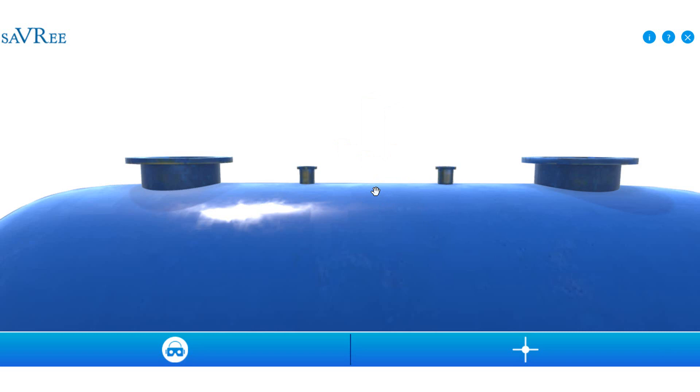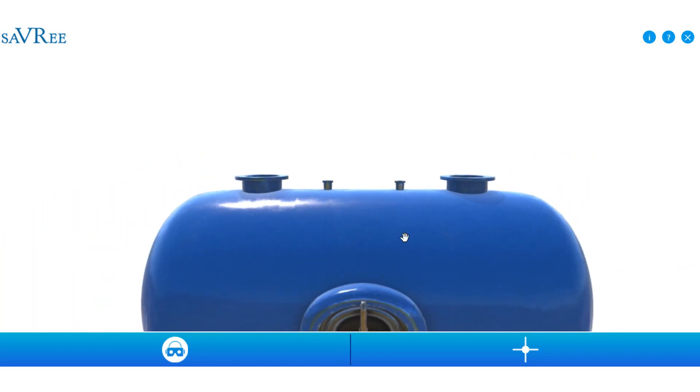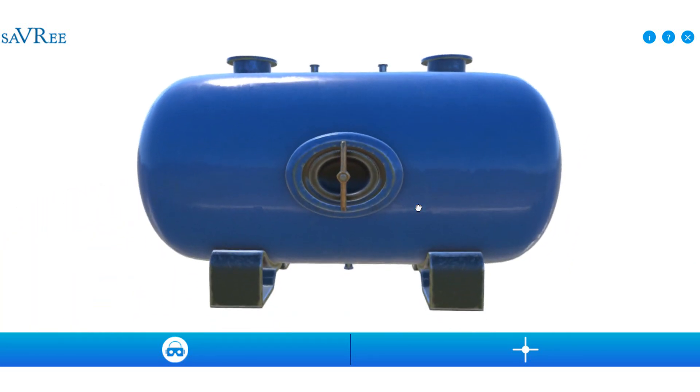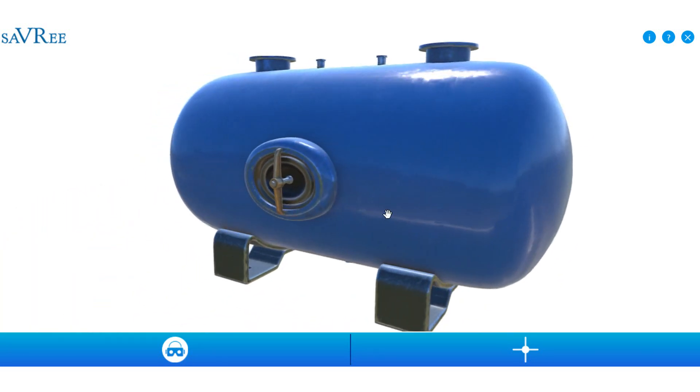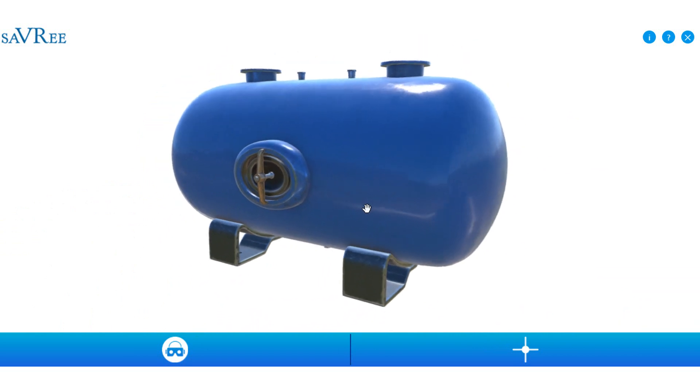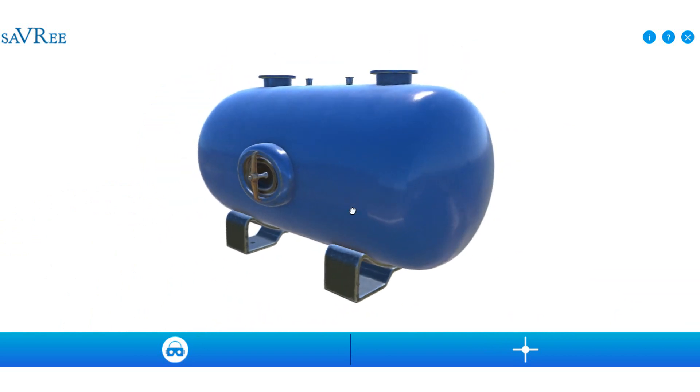And if the fire in the area was to heat up that fusible plug, we already know that the fusible alloy in the middle would melt and the compressed air would leak out or be forced out and vent to atmosphere. So it's reducing the risk of an explosion should there be a fire.